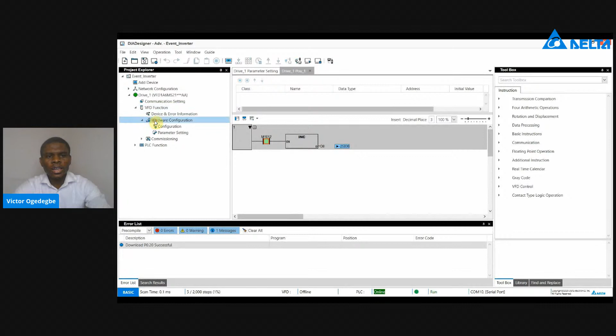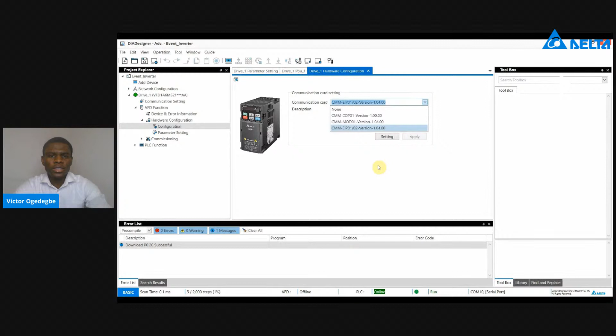The second feature I'd like to show to you is easy configuration. It is very easy to configure your inverter using the DIADesigner. If you go to the VFD function, expand the tree, go to hardware configuration and then configuration. If you open this configuration page, here you can easily configure the communication protocol you're going to use on your inverter. Here you can choose the communication card. It could be CANopen, Modbus, or EtherNet/IP. And once you have done this, the inverter could be a slave to a master PLC in your project. Easy configuration. And this easy configuration feature also applies to the parameter setting, like I showed to you earlier. So that's the second feature I'd like to show to you.